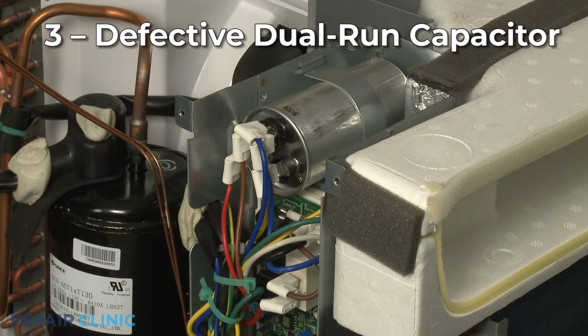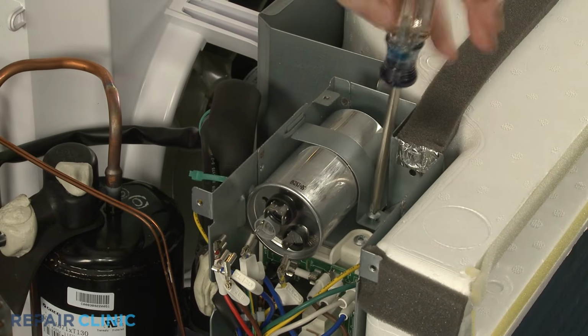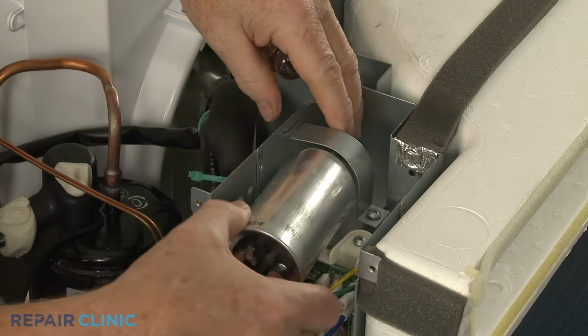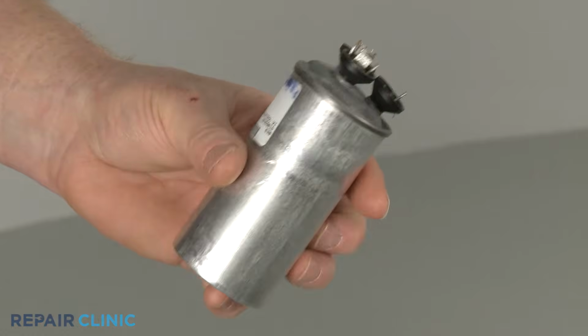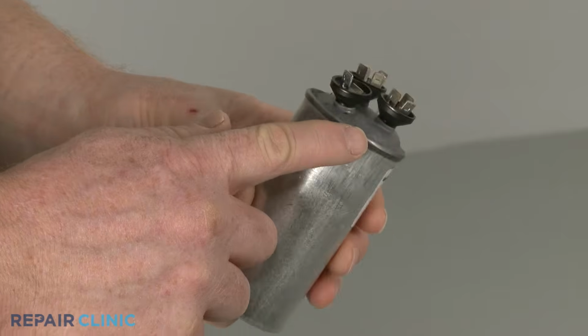A dual-run capacitor stores an electrical charge, then releases it to power both the compressor and the fan motor. If the capacitor is defective, the fan motor may not run. When a capacitor fails, it will often bulge or leak.